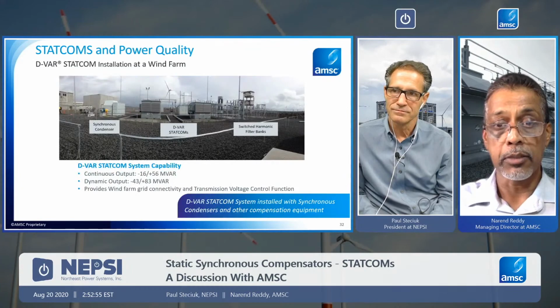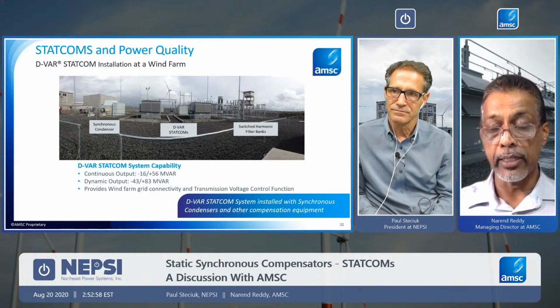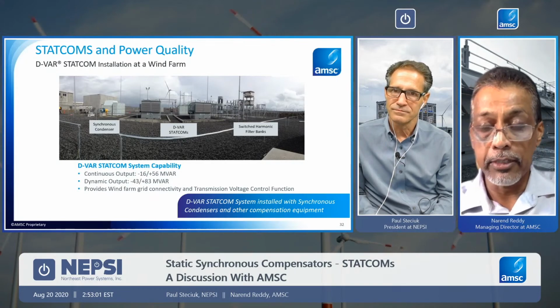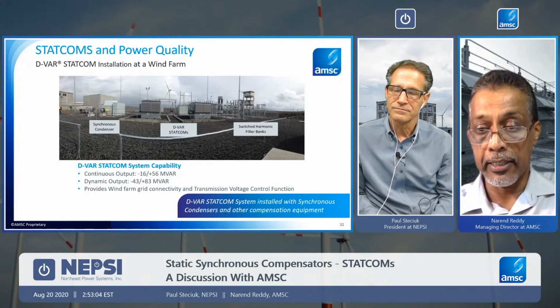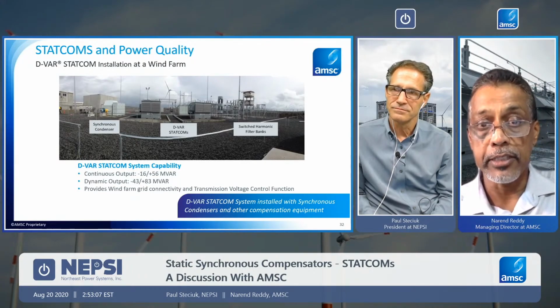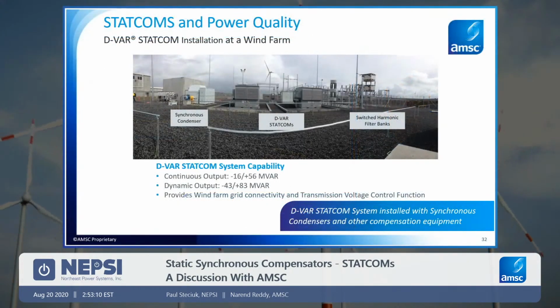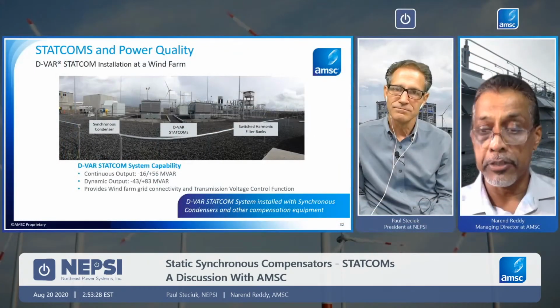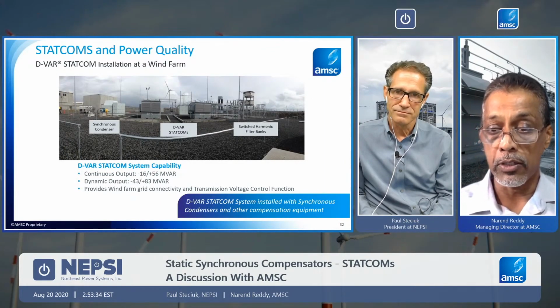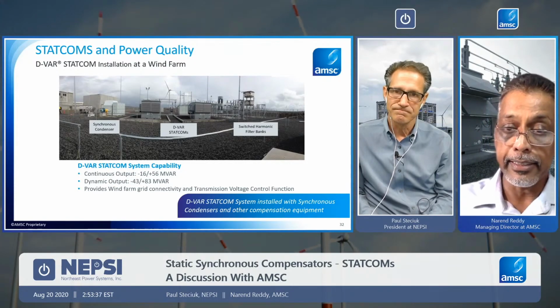It can be easily done. My point here is that these are things we've really gone through and done. In this picture, you can see that same wind farm. You have a synchronous condenser installed, 2 STATCOM units, and on the right-hand side, you'll see the open air cap banks, but more filter banks. You'll see the resistor units on those insulator posts. So from a harmonic standpoint, it is really something manageable that we can do. It's just a matter of understanding what the overall application and the overall background needs are.